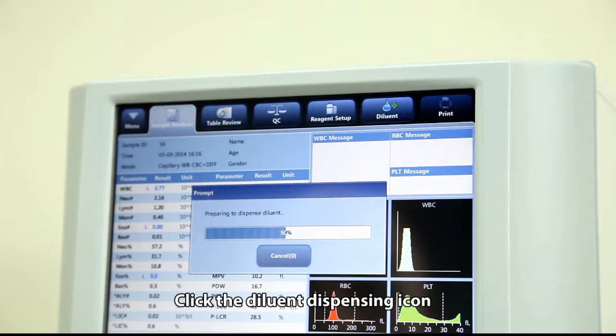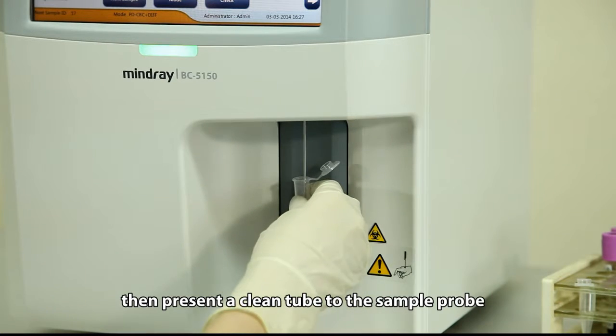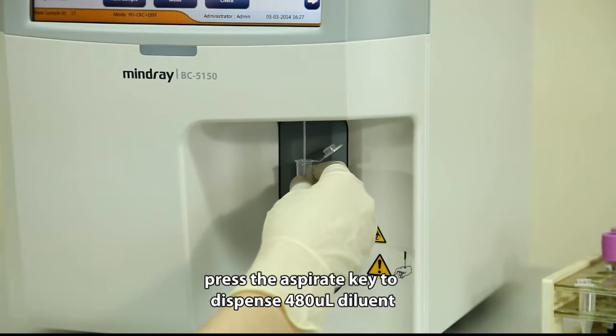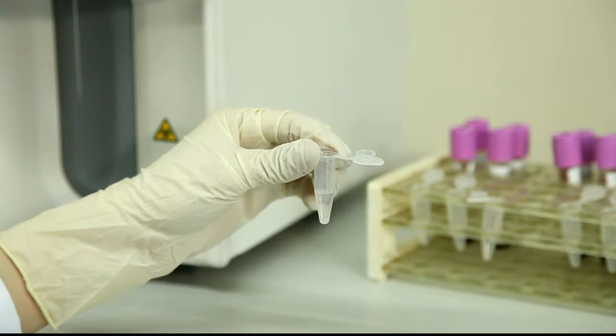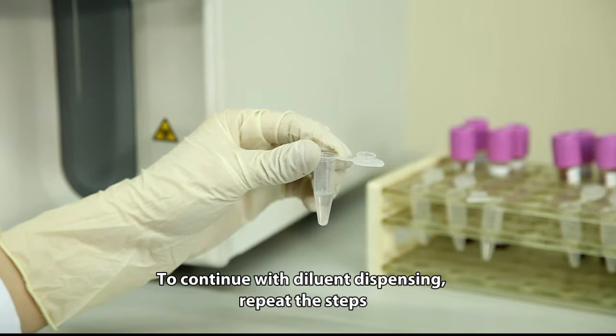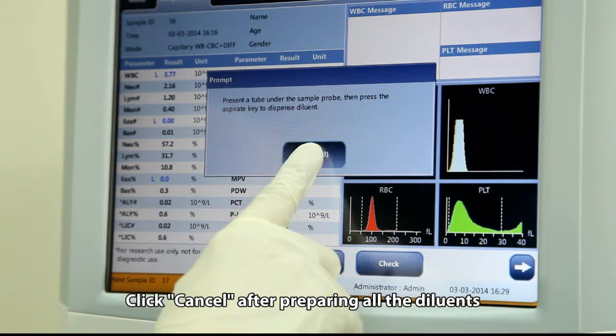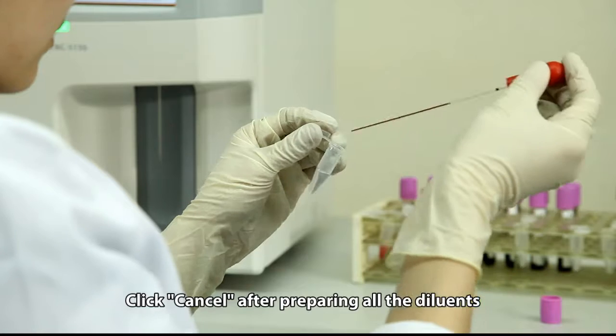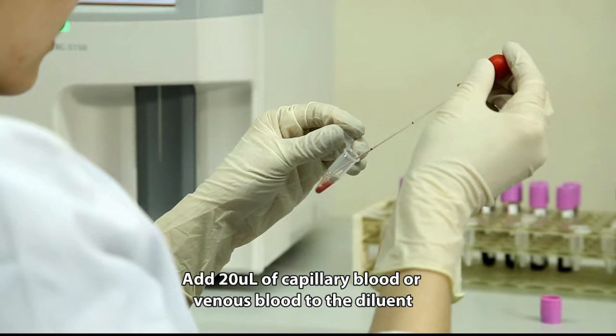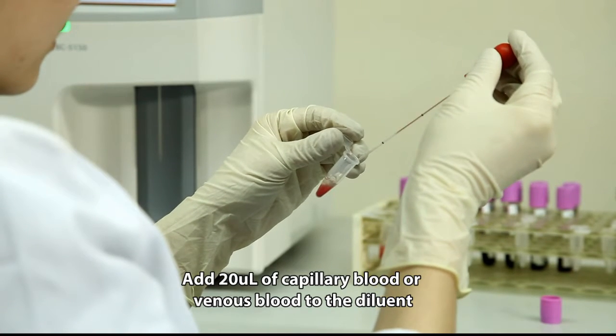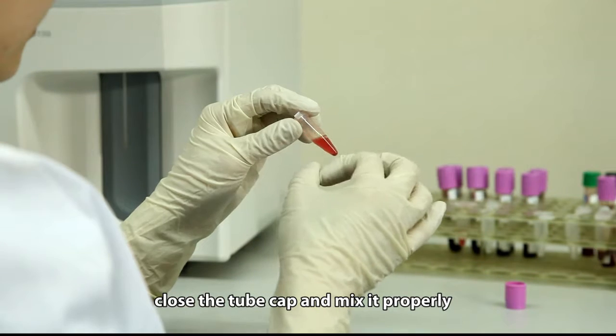Click the diluent dispensing icon, then present a clean tube to the sample probe. Press the aspirate key to dispense 480 microliters of diluent. To continue with diluent dispensing, repeat the steps. Click Cancel after preparing all the diluents. Add 20 microliters of capillary blood or venous blood to the diluent. Close the tube cap and mix it properly.